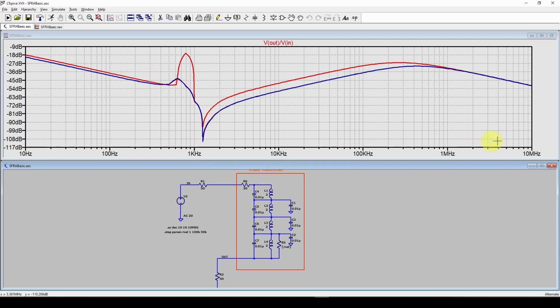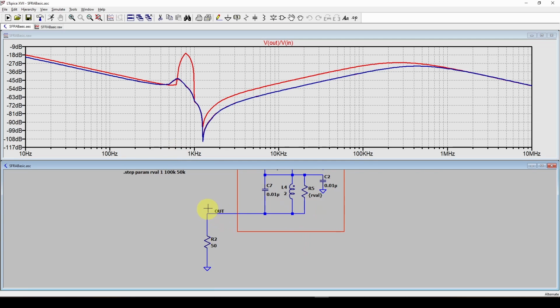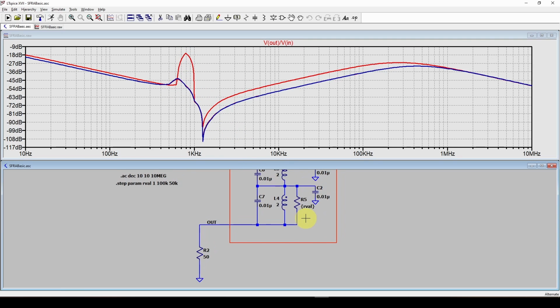Here we have from 10 hertz to 10 megahertz, and you can see the impedance changes a lot, which means this output voltage we're measuring is going to change with frequency. If you have, for example, the resistance of a shorted turn, you might see a big spike or a big change from what you got without that.